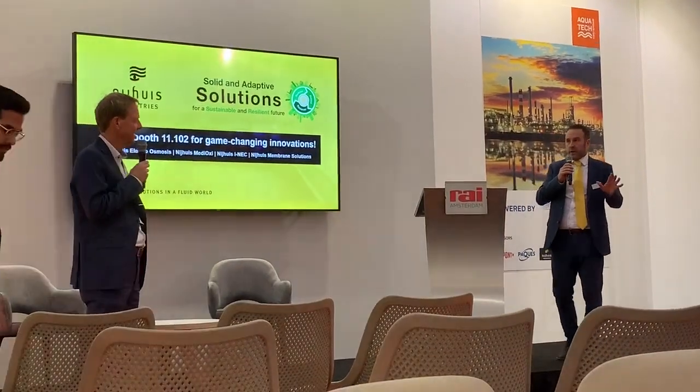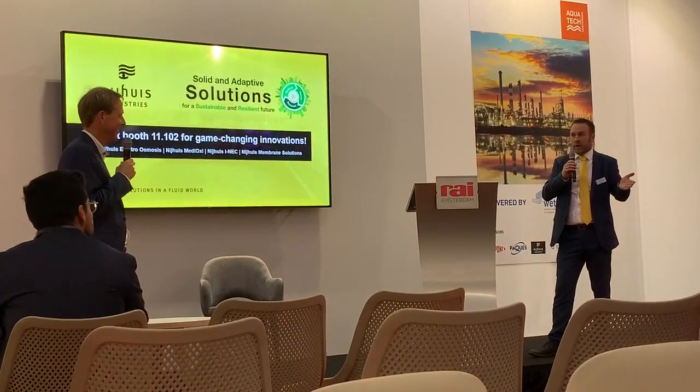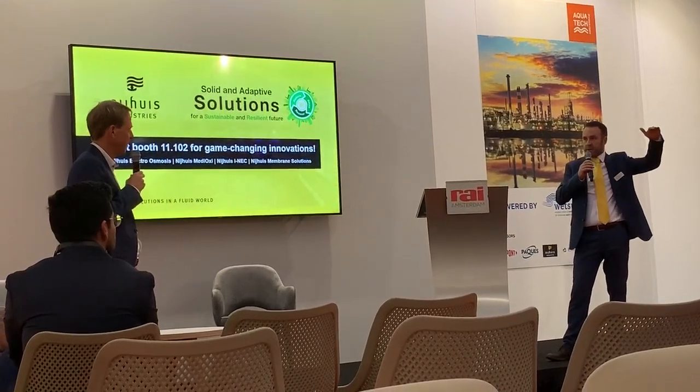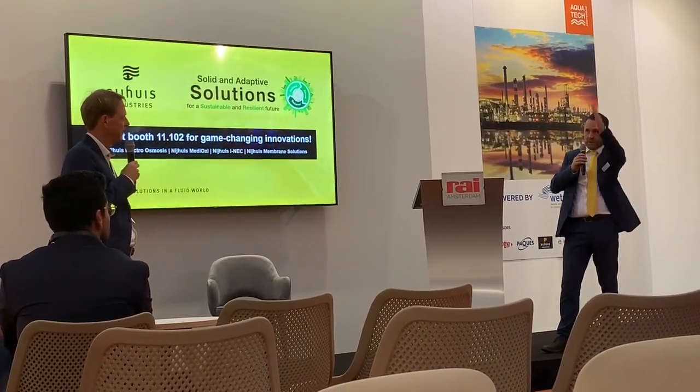And we managed the client's expectations. Like, we knew that this would happen, and they were expecting that. So what we did was, for the initial 3 to 4 days, we just raised the bromine and disinfection levels, because we knew that the COD would effectively spike and then drop down again.